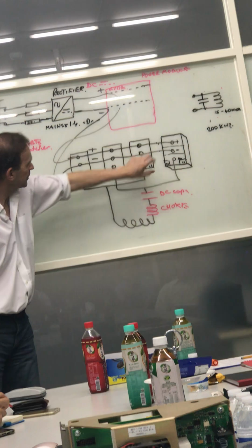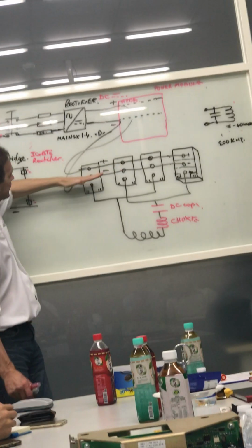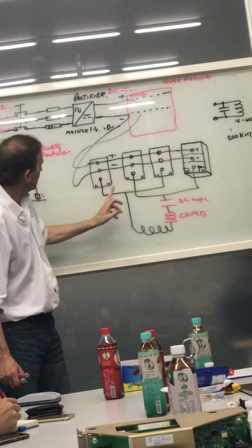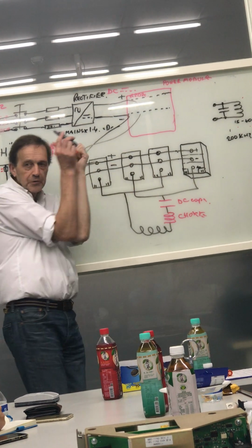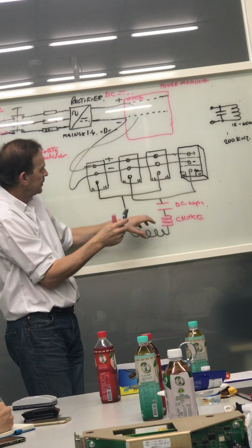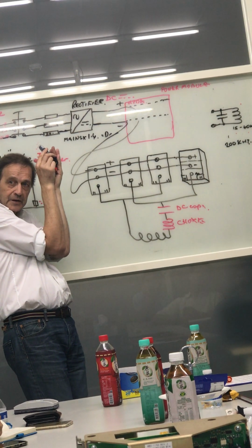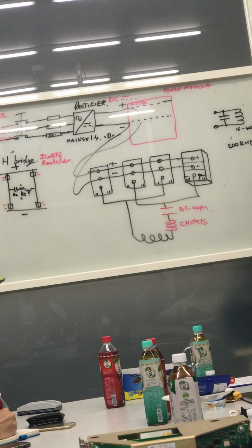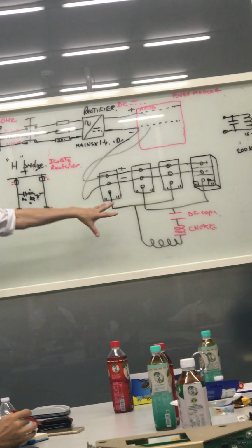So you've got your IGBTs, you've got all of them linked in the form of copper work or copper assembly, and then you've got linked copper assembly, which are really close together with insulation to stop any stray inductance. So you won't have them like this. You'll notice that all the copper plates are very close together. And it's important that it stays like that as well.